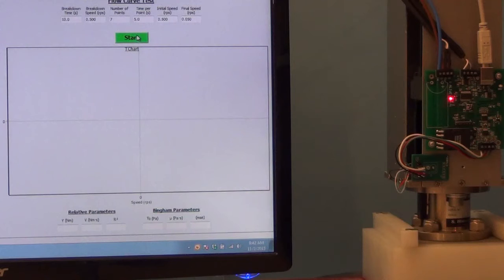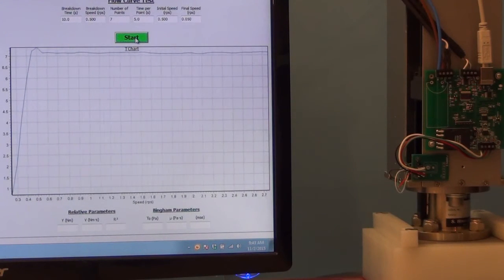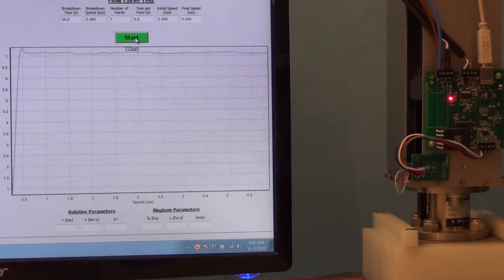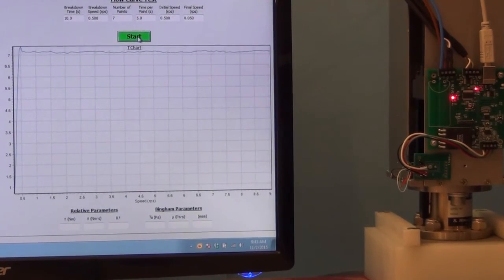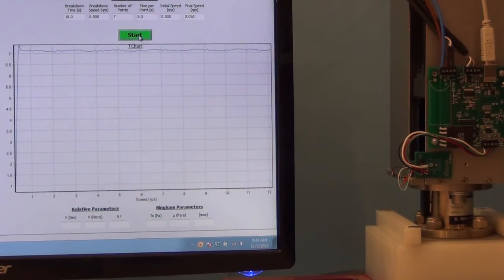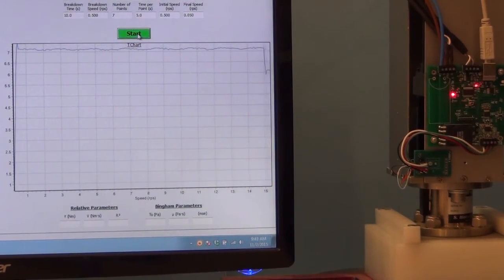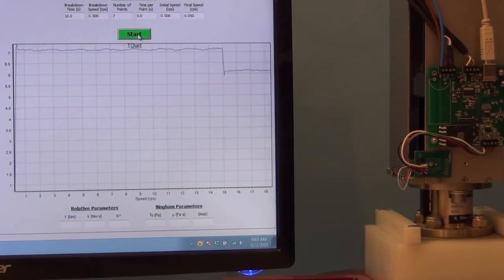Alright, so our flow curve test is going to have a breakdown time of 10 seconds, a breakdown speed of 30 RPM. It's going to capture 7 points. It's going to stay on each point for 5 seconds. The first point is going to be taken at 30 RPM and the last at 3. Alright, so here we go. Alright, so we expect to stay at this basic level until we get 15 seconds into the test. That's the 10-second breakdown plus the first 5 seconds for the first step. There we go, right at 15 seconds. And now at 20.